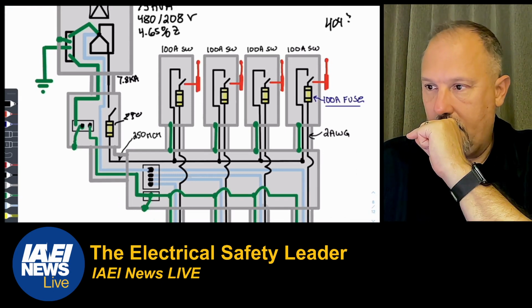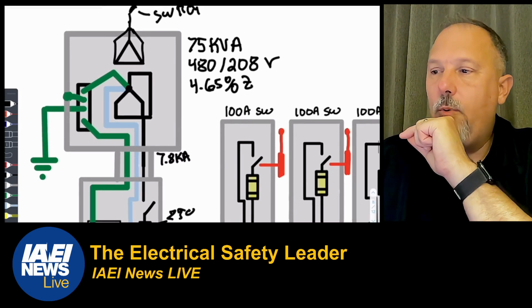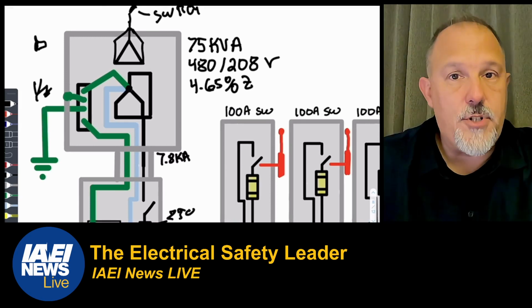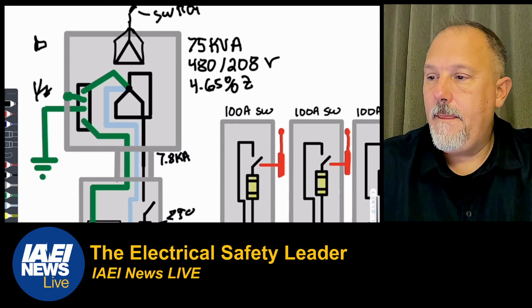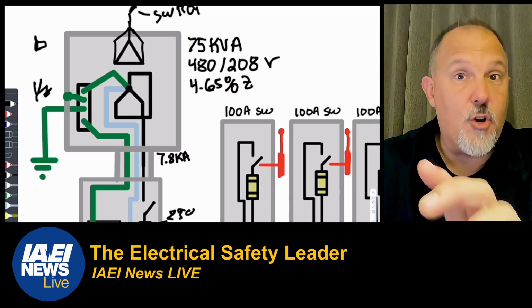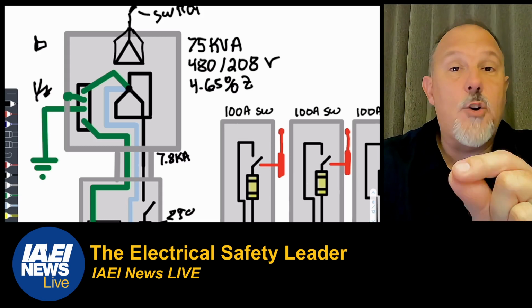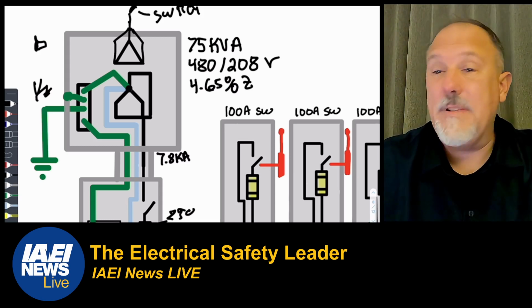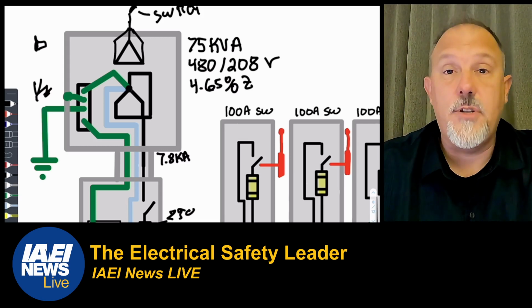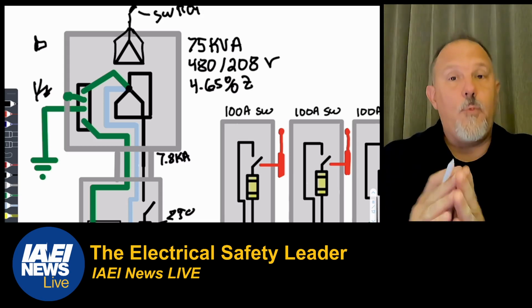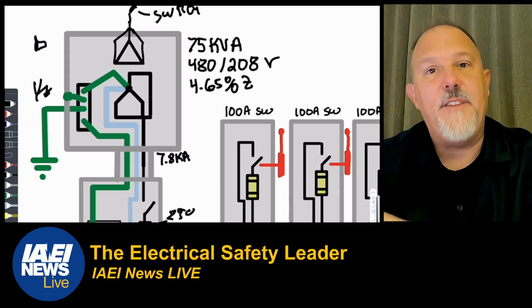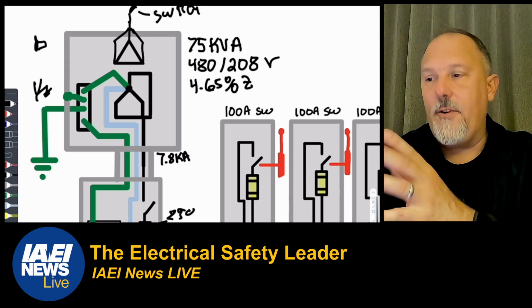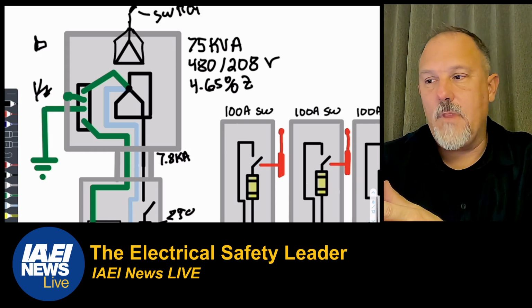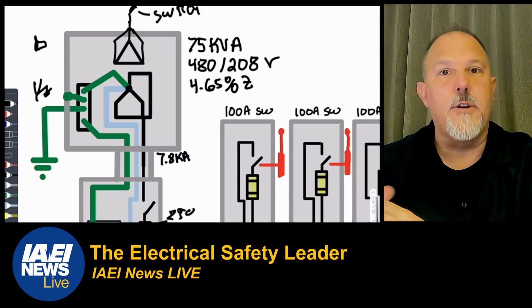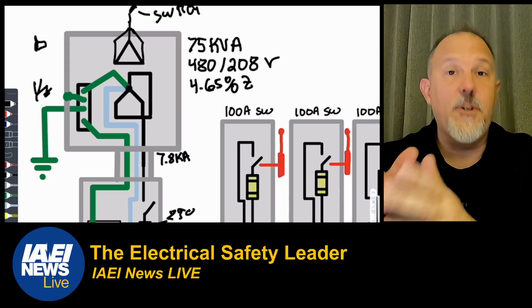Now, let's start up here in the transformer. We have a delta Y transformer. We've got a delta Y ground. And remember I told you that the bonding of the neutral, the grounded conductor, is bonded with the equipment grounding conductor, is bonded with the grounding electrode conductor, which gets you to the grounding electrode. So what differentiates that separately derived system is where you're bonding all of these aspects from a grounded conductor, an equipment grounding conductor, and how you treat all that. And we always ground in one spot.